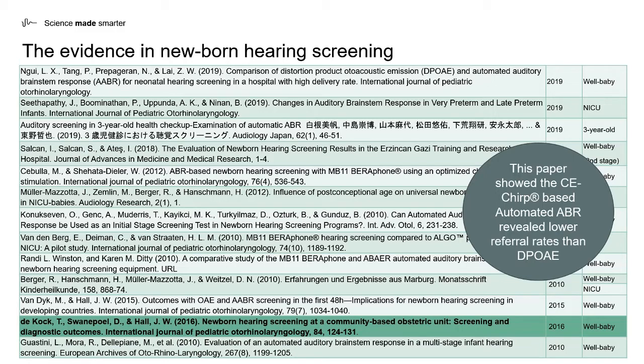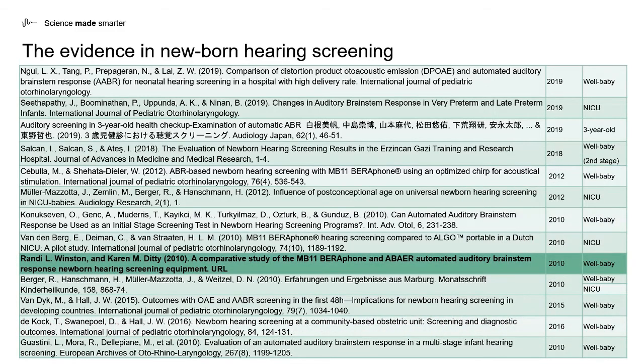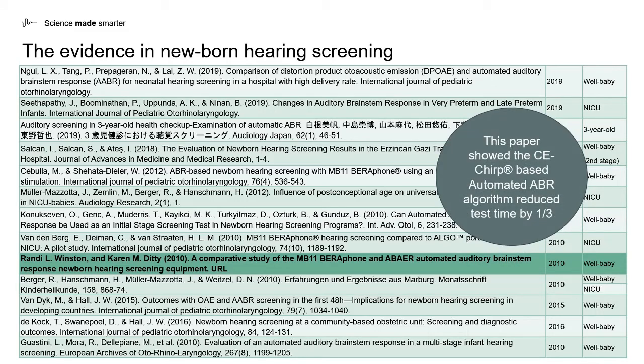The last study I want to highlight addressed test time when using CE CHIRP-based algorithms as opposed to non-CE CHIRP-based algorithms for detecting the automated auditory brainstem response. What this study showed was that by using the CE CHIRP and benefiting from the larger response amplitudes, this resulted in a test time which was reduced by one third when compared to algorithms which used click responses.